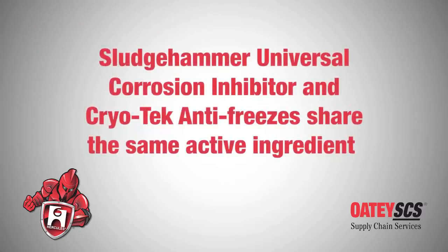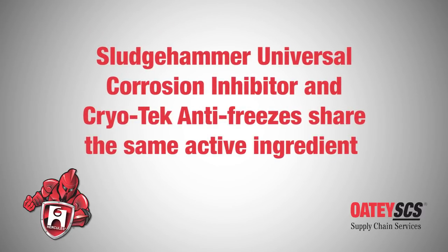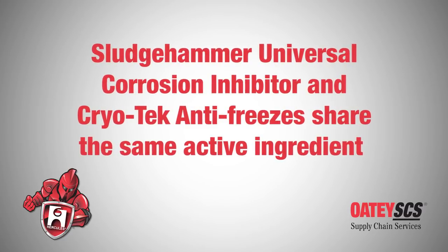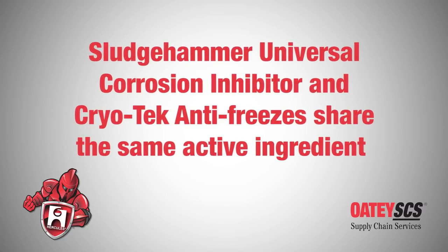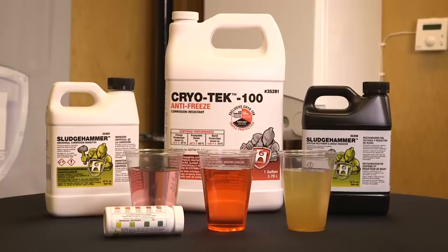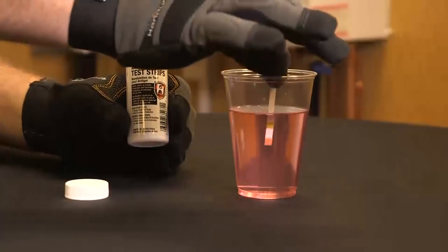Sludgehammer Universal Corrosion Inhibitor and Cryo-Tek antifreezes share the same active ingredient, allowing an accurate reading of the total level of corrosion prevention when testing the fluid currently in the system. There are three possible results.